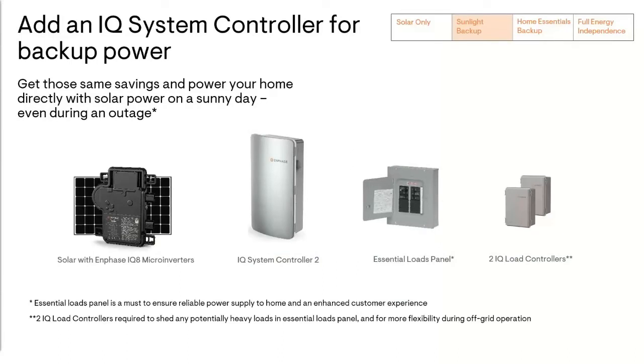Because of the variability and how that can impact the performance of the system, we require the installation of an essential loads panel with a recommended maximum of 4 120-volt circuits. During an outage, only the essential loads panel will be powered by the sunlight backup system. We also require the installation of 2 IQ load controllers. This is a new product I'll go into more detail about later, but each load controller can control the power supply to 2 circuits. So by installing 2, you can control power to all 4 circuits in the essential loads panel. There will be a new load control setting available for the essential loads, which is designed to improve the stability of the microgrid and the homeowner experience with the sunlight backup system.